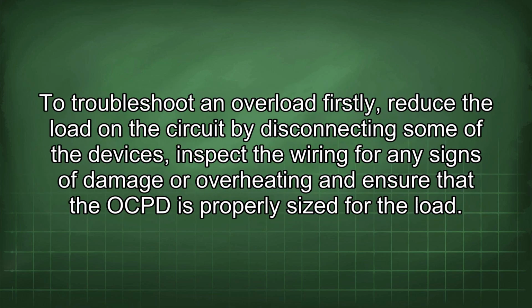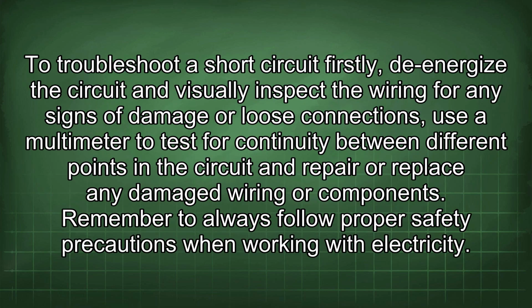To troubleshoot an overload, firstly, reduce the load in the circuit by disconnecting some of the devices. Inspect the wiring for any signs of damage or overheating, and ensure that the OCPD is properly sized for the load. To troubleshoot a short circuit, firstly, de-energize the circuit and visually inspect the wiring for any signs of damage or loose connections. Use a multimeter to test for continuity between different points in the circuit and repair or replace any damaged wiring or components.